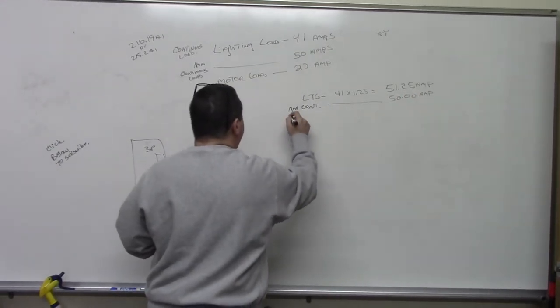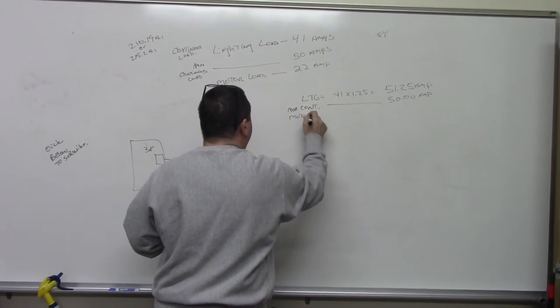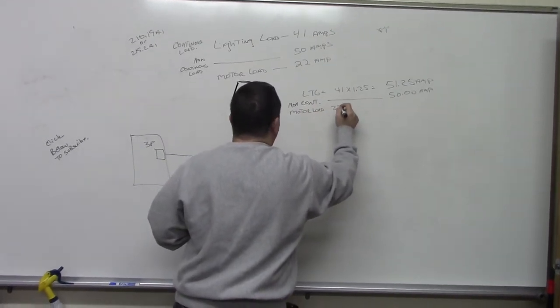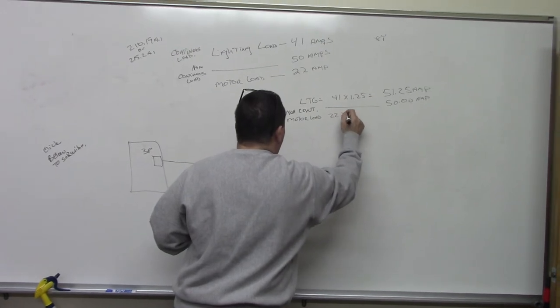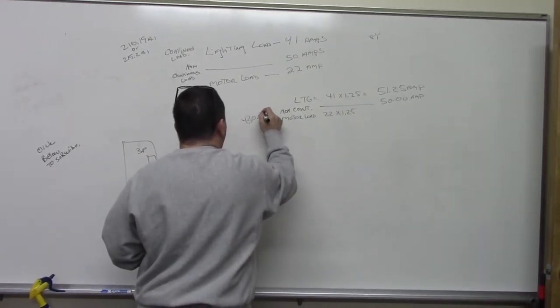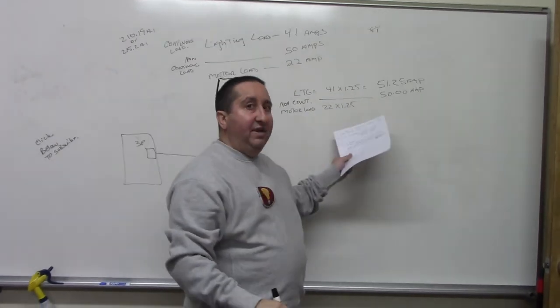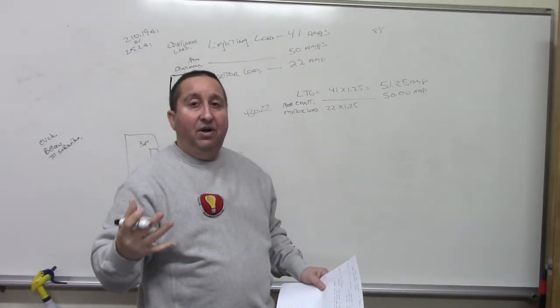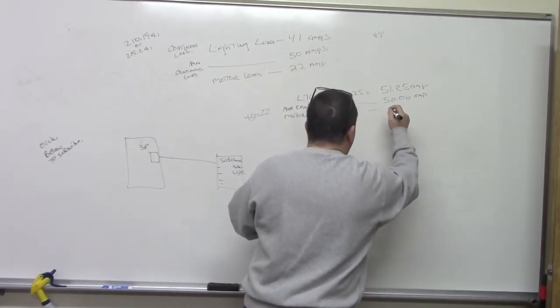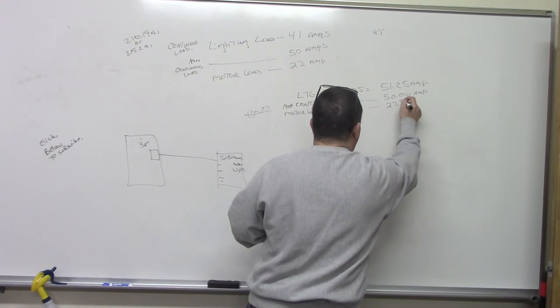And then we have the motor load. And it's 22 times 1.25. And you'll find that in 430.22. Again, for the startup and everything for the motor, you allow 125%. So when we do that, we come out with 27.50 amps.